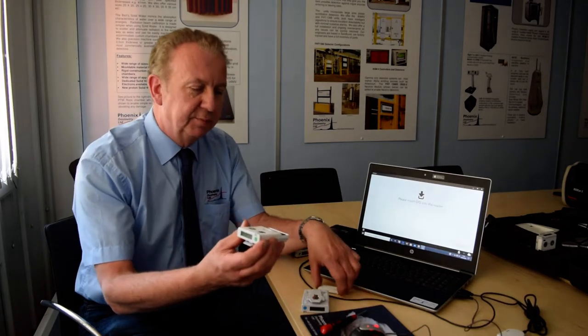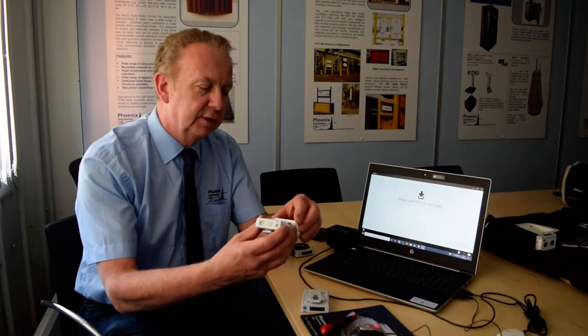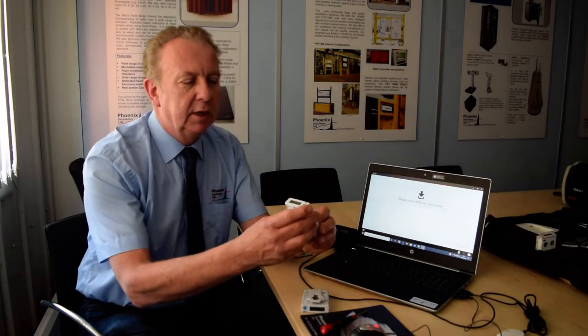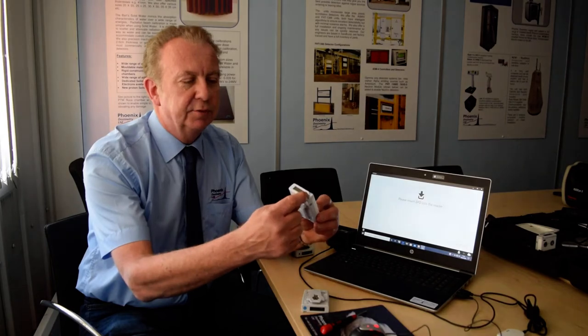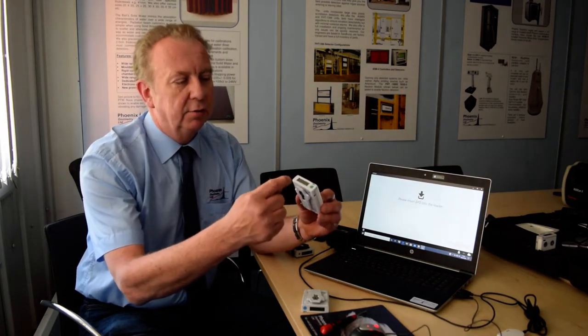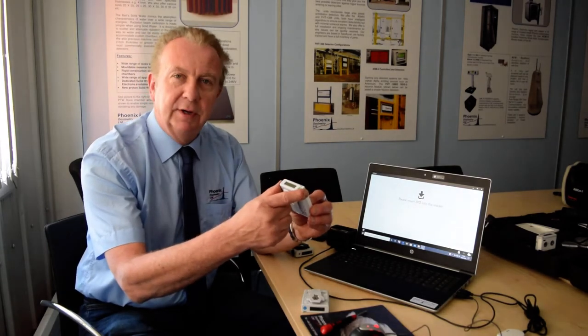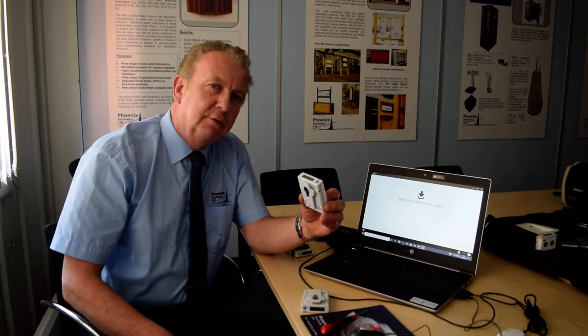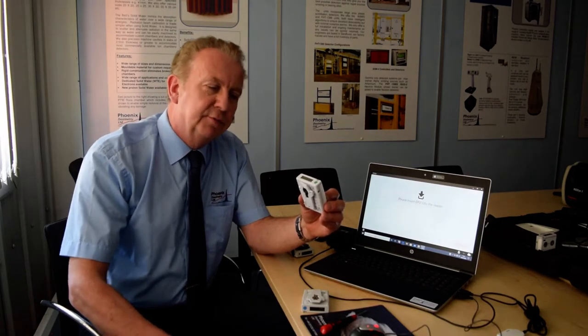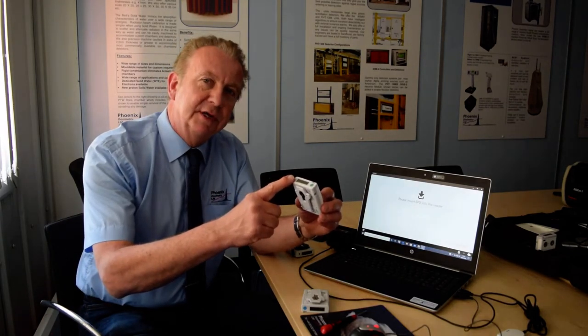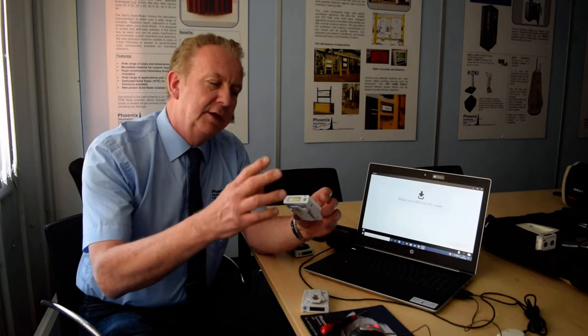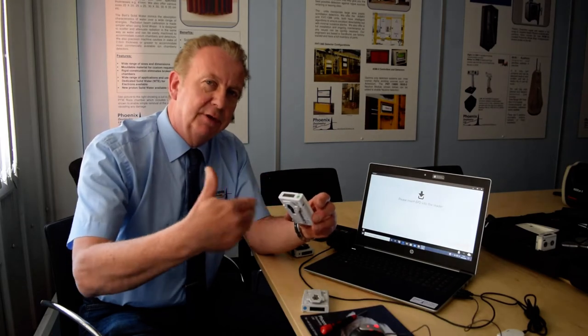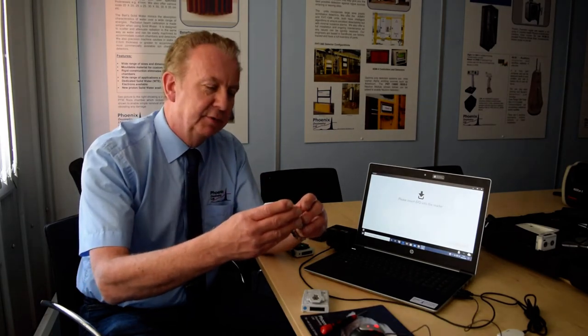When I put the battery back into the unit, it'll go through a self-test. As you can see, this one's got an LED, also a vibrate and a sounder. All of these are adjustable, the sounder's adjustable up to 100 decibels, and you can configure how you want the alarm to actually go off when you set the system up on the software.